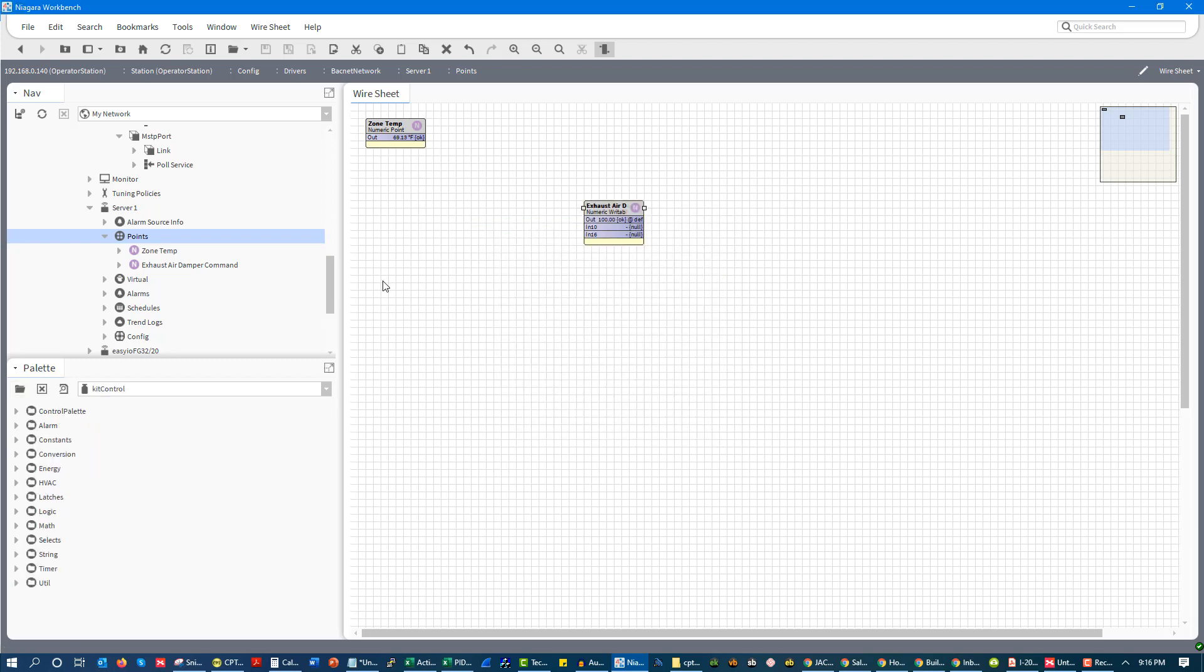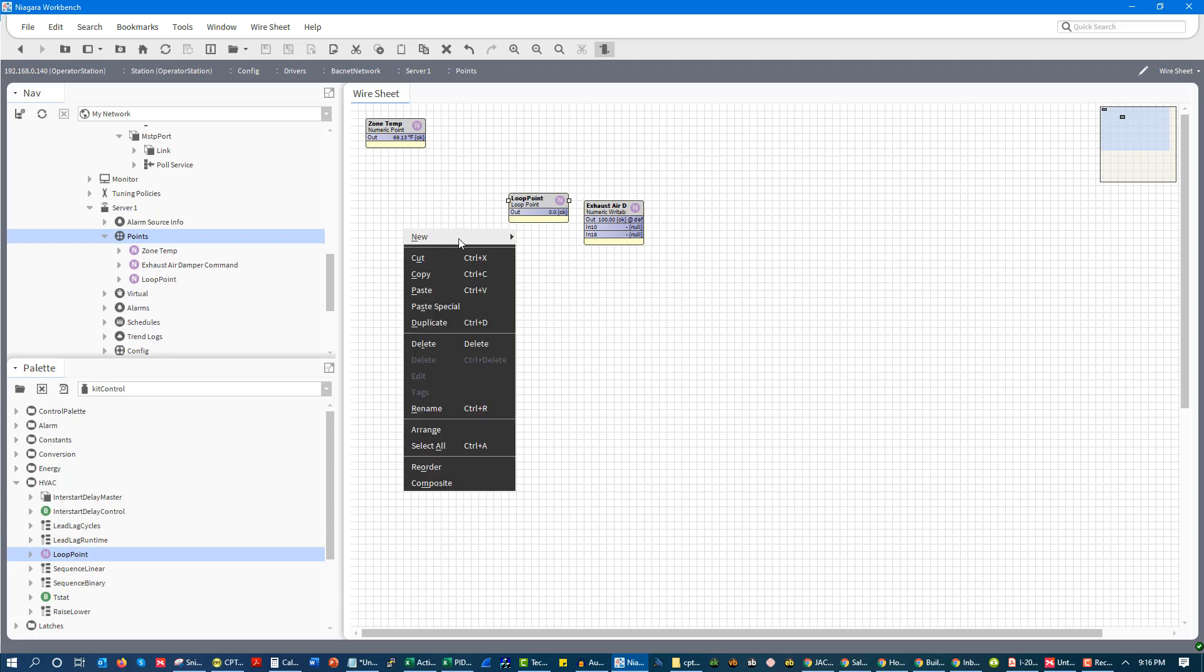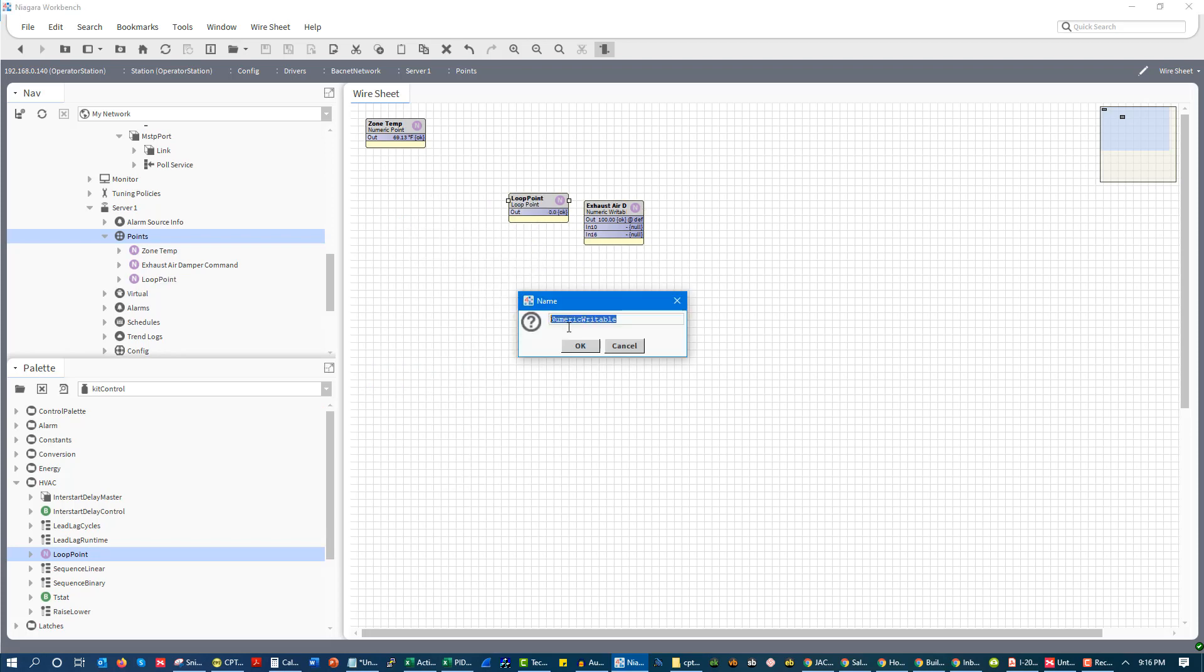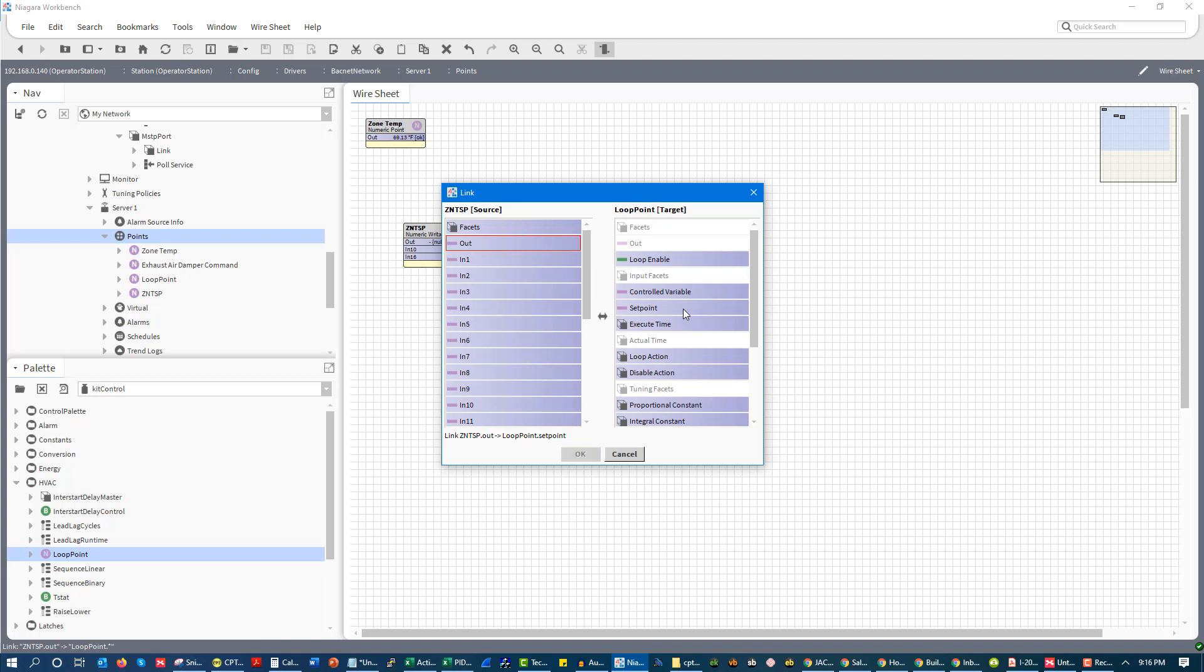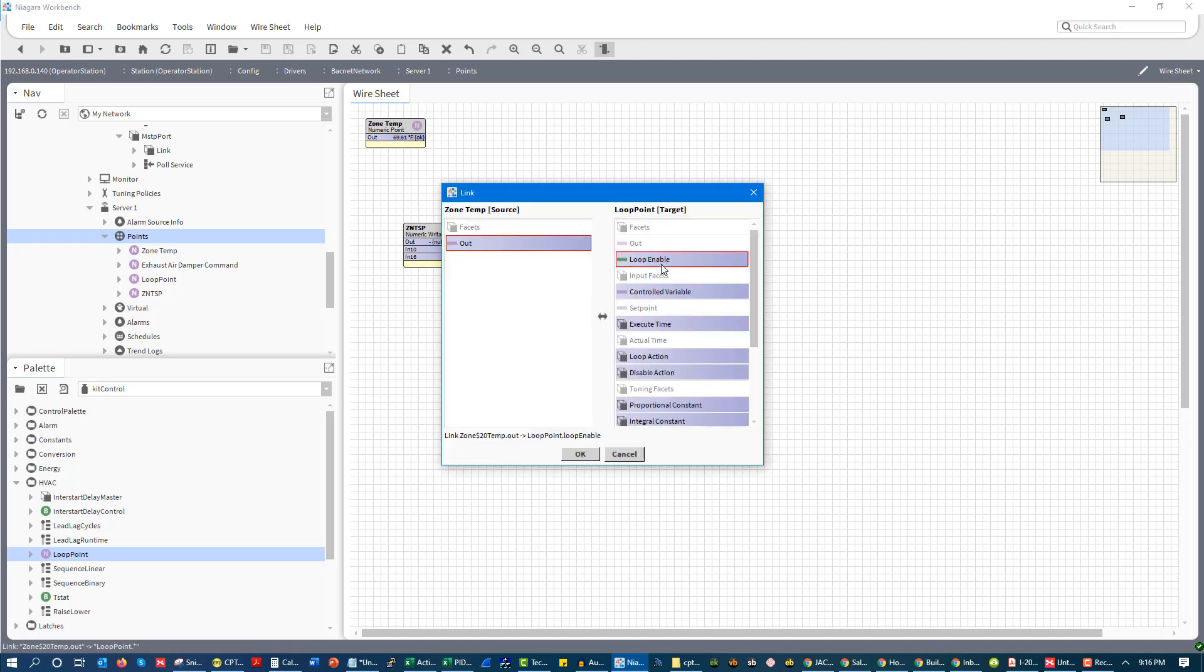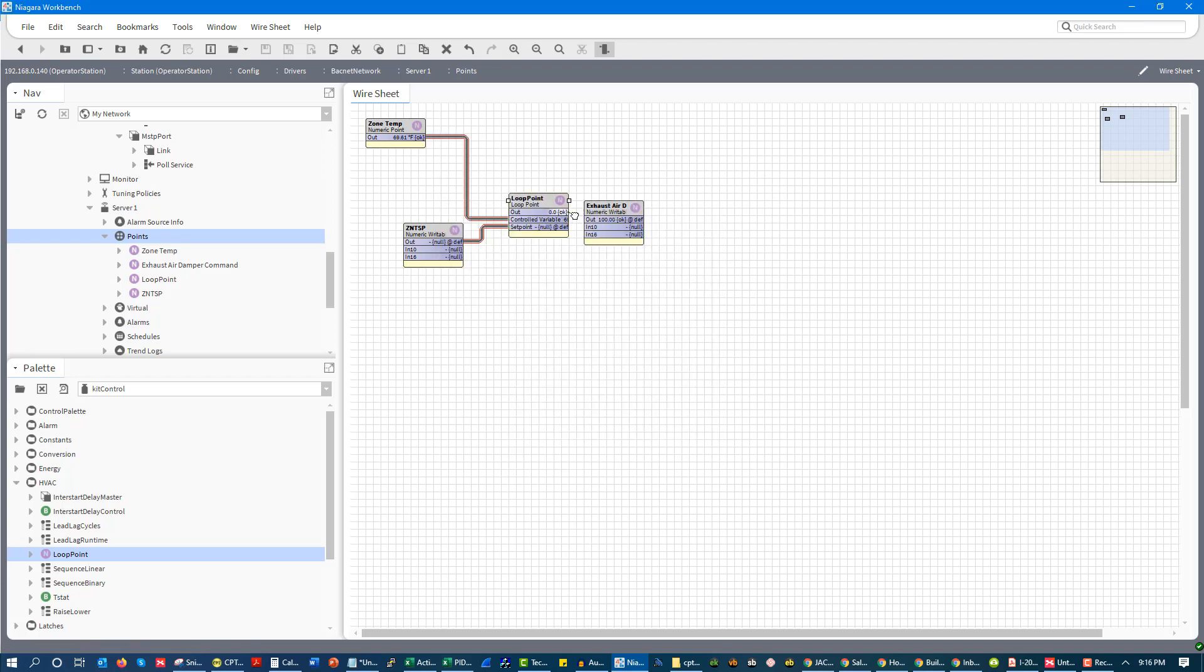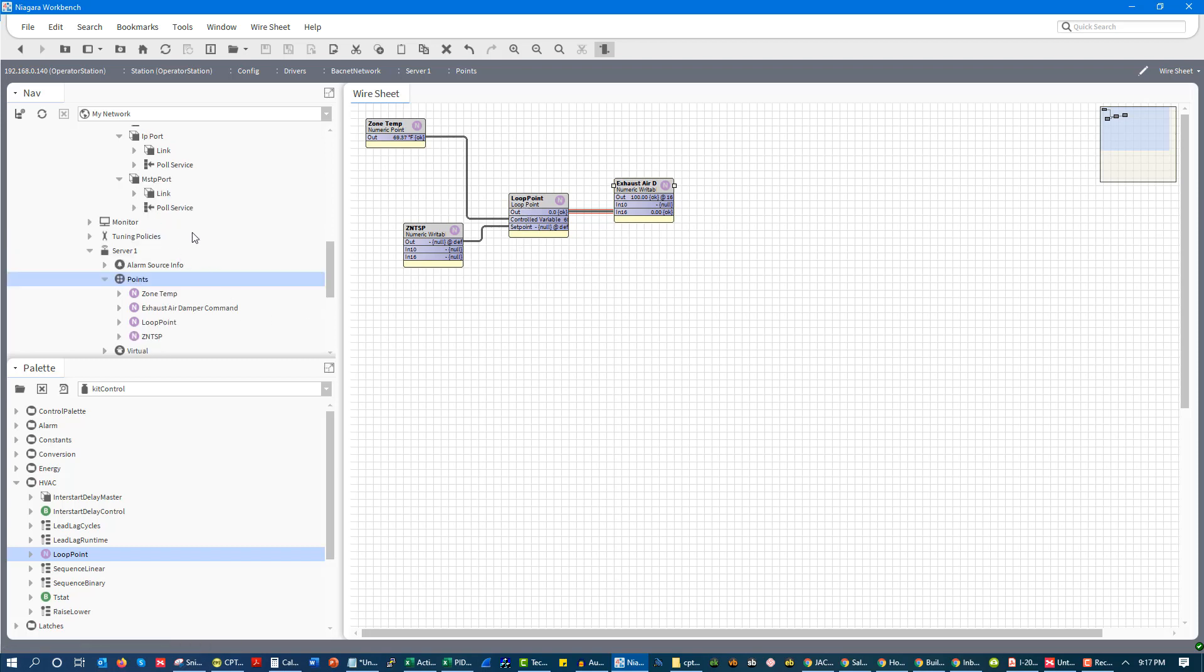I can then go into my actual programming, so I can open this up, and I can start to write logic. If I wanted to, I could have a PID loop, and I could have a set point. And that set point could come in right here, and then my point right here could come into there. And then I could go and drive my exhaust air damper based on the difference between zone set point and zone temp. Obviously, there'd be more setup to this. But that's how this works. You go and you have your trunk. You discover your devices. You discover your points. And then you map this all in.